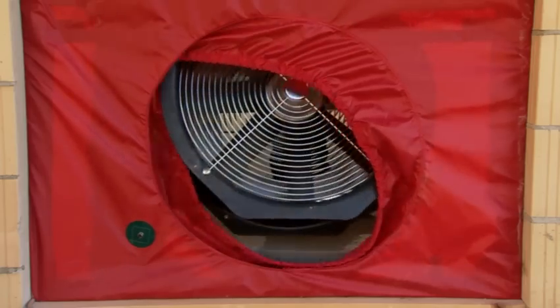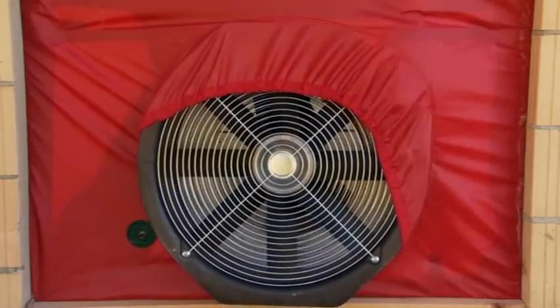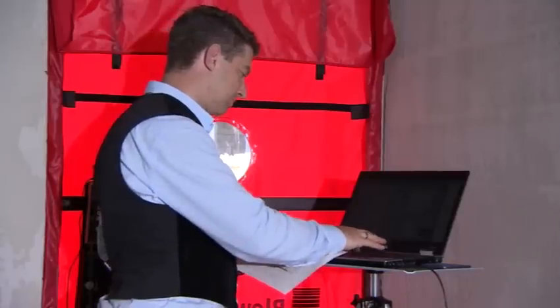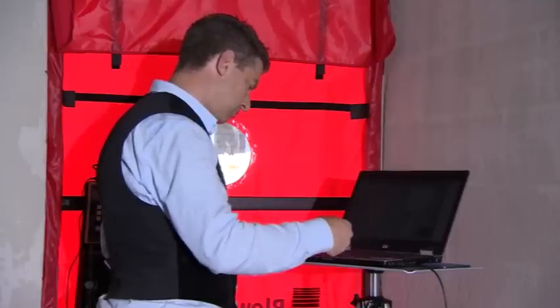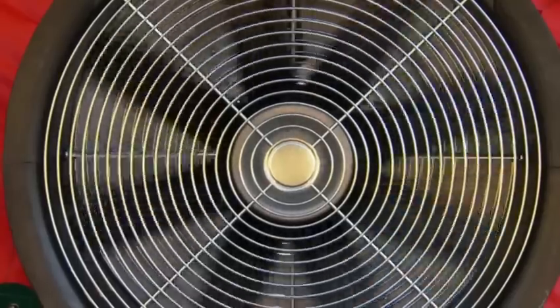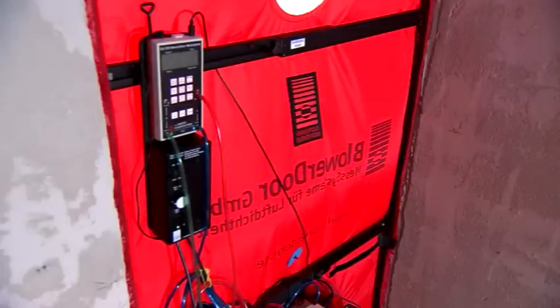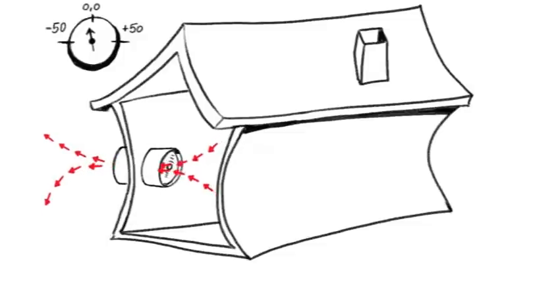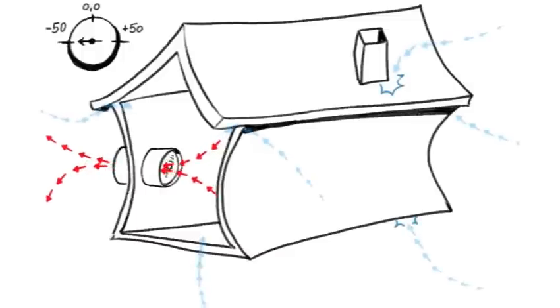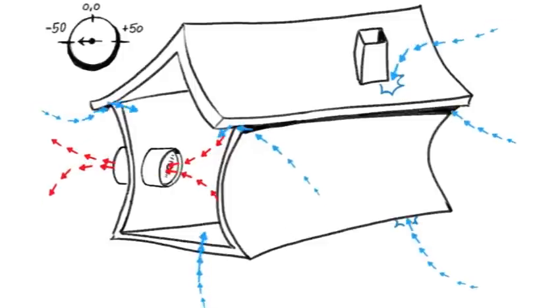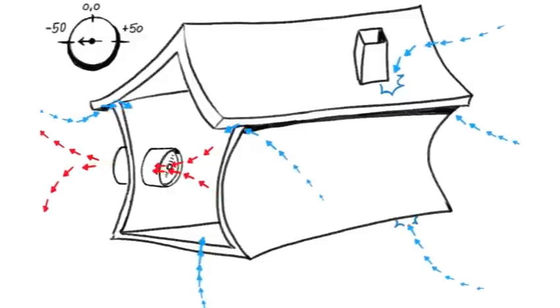The main component of a blower door test set up is a powerful fan. The fan is installed in the opening of the membrane. The values required for measuring are programmed in and measuring begins. Negative pressure builds up inside the structure. The membrane at the measuring apparatus bulges inwards. The fan blows the indoor air out of the structure to produce a negative pressure of 50 Pascal in the interior. Through leaks in the building envelope, cold air flows into the house. It is the tester's job to determine how much air flows in via the envelope surface and how much is blown out by the fan.